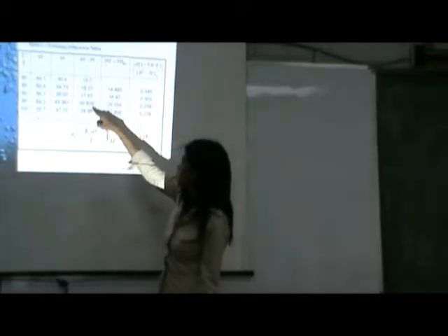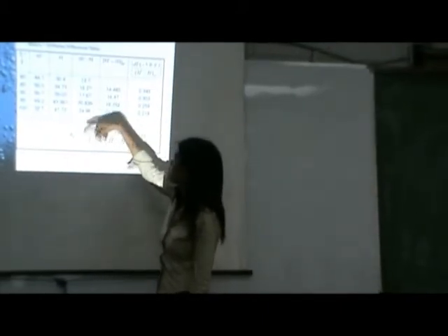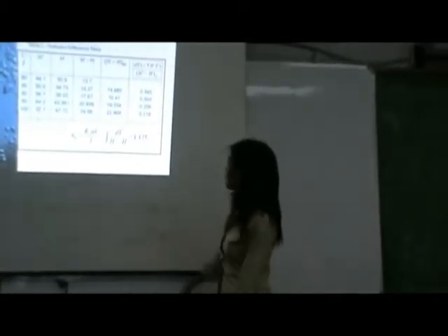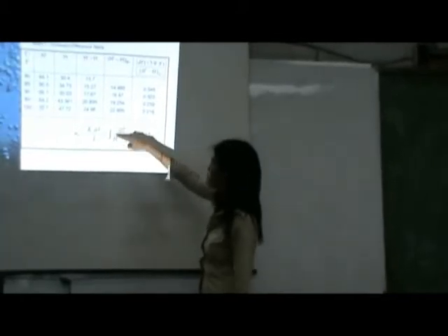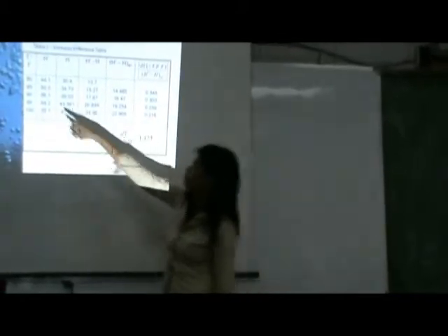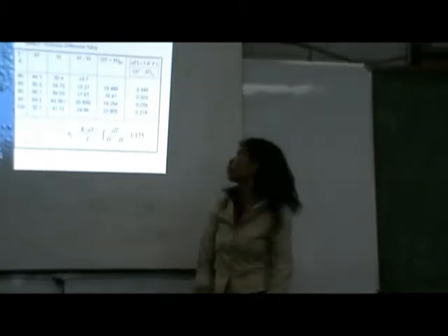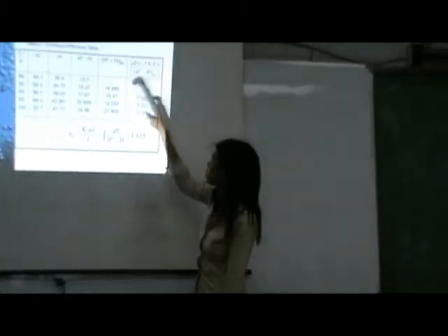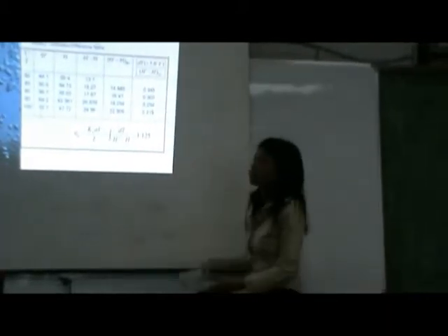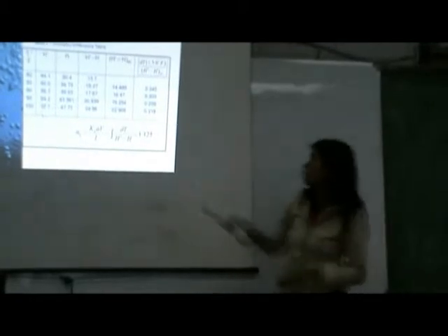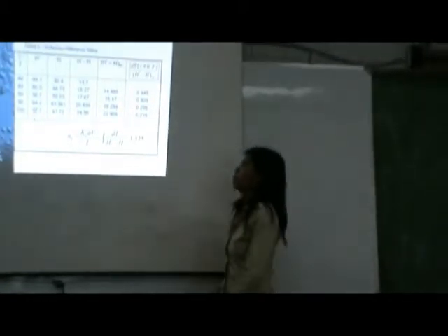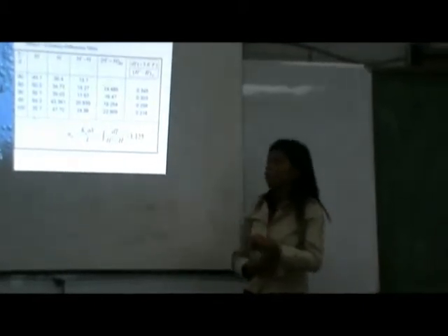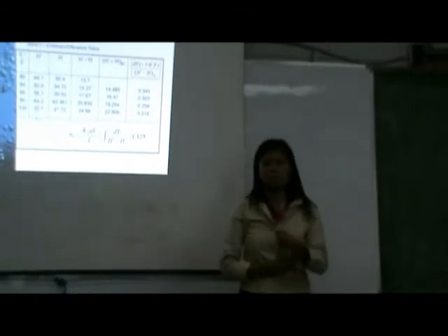Then we will have these values and average the first two values consecutively to get H prime minus H average. Then we use these values in our equation by getting dT, which is just 5 degrees since our interval is 5. So here it is 5 all over H prime minus H average, which is here. And then we will get these values. By integration, we just add these values to get our KaV over L. So we will get 1.125 for our tower characteristics by numerical integration.